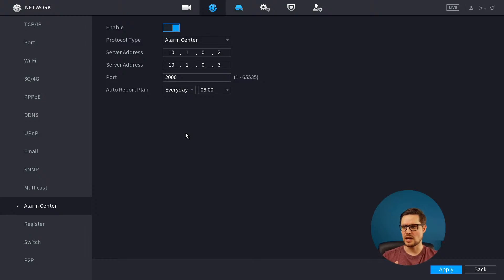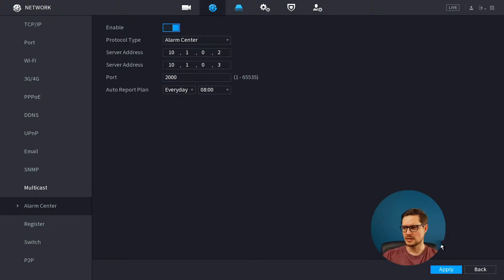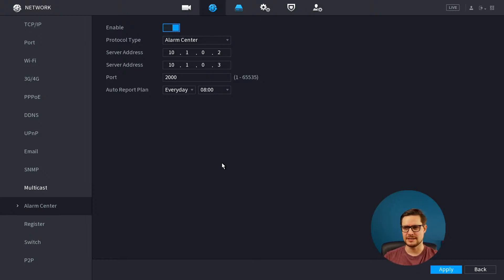The monitoring station will provide you with all the details to enter on this page, together with the SMTP server, port number, receiver email address, and a subject — it could be an identification number or something like that. Once all the settings are done, click the test button to check the connection; if the email is working you should get an OK message. The other option is the Alarm Center — if the monitoring station provides an alarm server address, that's where you go. You just need to make sure it's enabled, enter the server address and port number, and click apply.